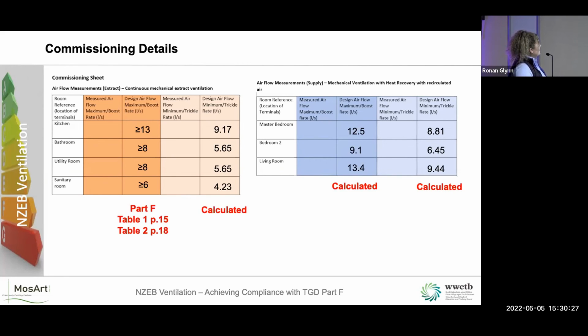You're allowed to have a tolerance on them. So if it's a reading above 10 litres a second, you're allowed plus or minus 10%. Anything that's above 10 litres a second. If it's below 10 litres a second, then you're allowed a 1 litre a second tolerance on that reading, okay? And I'd always be saying to lads, leave the tolerances for the validator. Let the commissioner get it pretty bang on and let the validator worry about the tolerances.